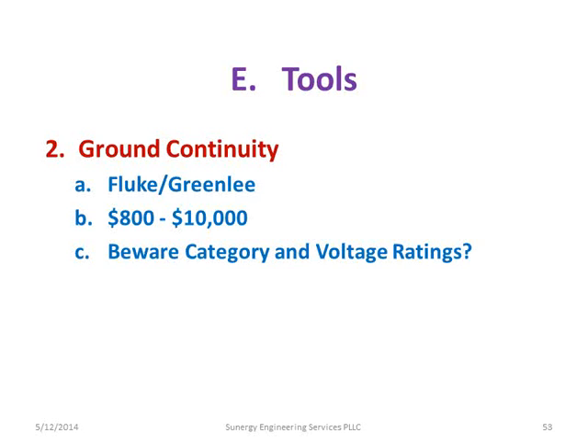And then you get into the actual ground testers. I mean, it's like the inspector says, if you can show that your ground's good, you don't have to use another ground rod. Well, the tester costs $12,000, so how much does a ground rod cost? That's easy, I'll just put another ground rod in. I'm not going to buy the tester, right?